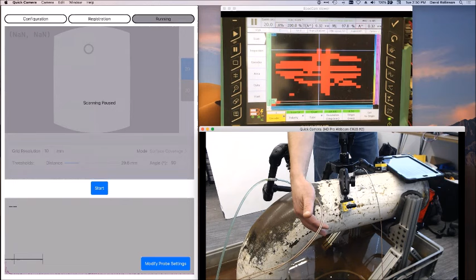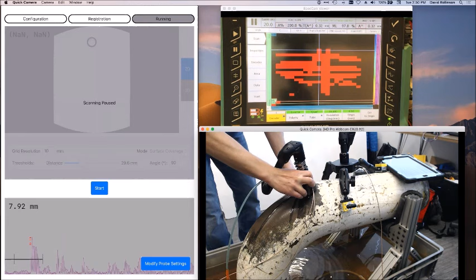And as soon as I start up my bubbler, you can see the A-scan down below. And as soon as I unpause, I can start moving over the surface and building up thickness as I go. So this is doing a 10mm grid, so a little bit tighter than a half inch.